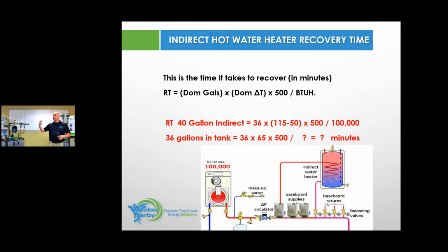So I go back like, when we're training live here, I had a guy right in the front row, and I know him for quite a while. He went home and did the math on his, and he came back with almost the same exact scenario. He figured out why he has insufficient hot water, and he was going to fix it. Easy fix, put his own Sentry in there, and you'll get the 95,000 BTU worth of energy going over to that indirect. Okay, so here we go. We're moving on.